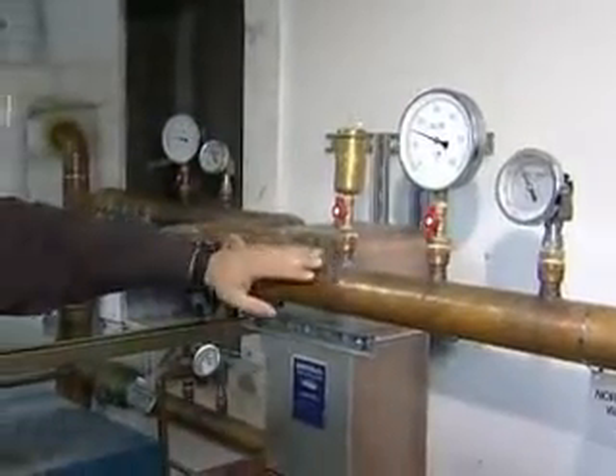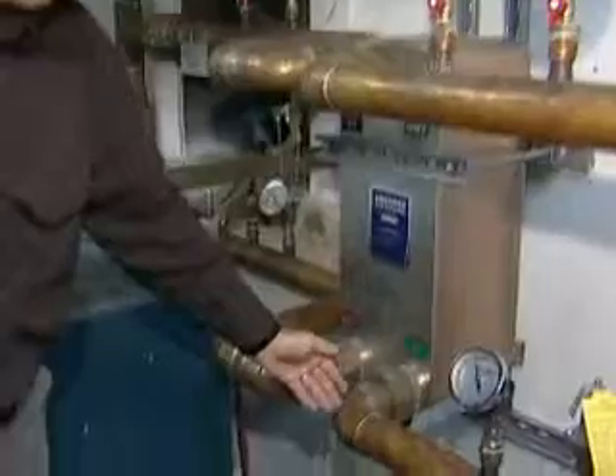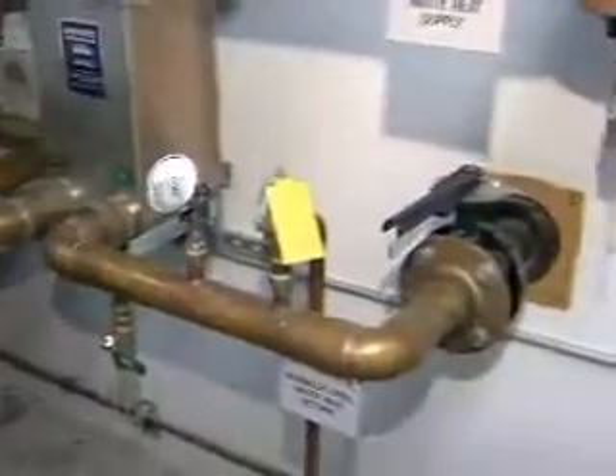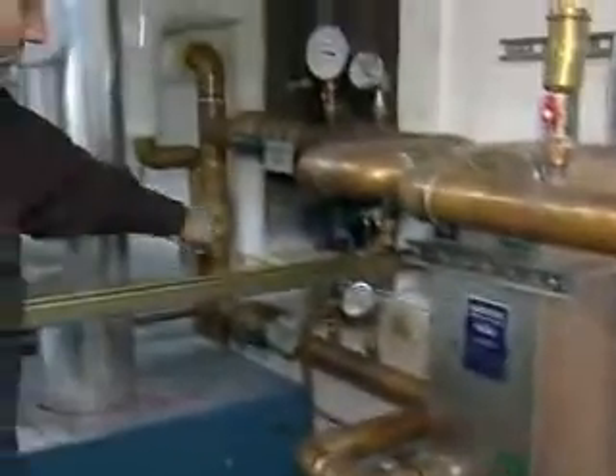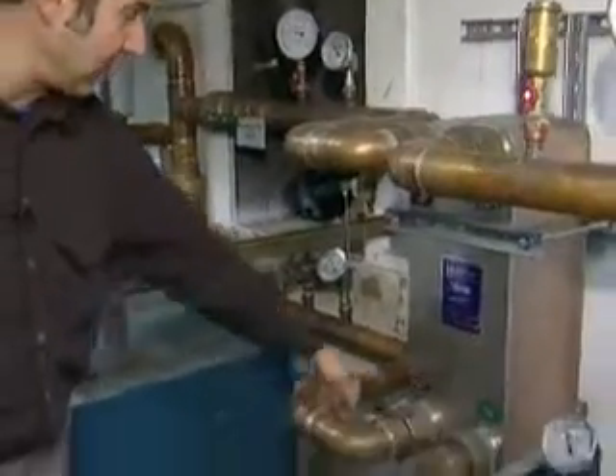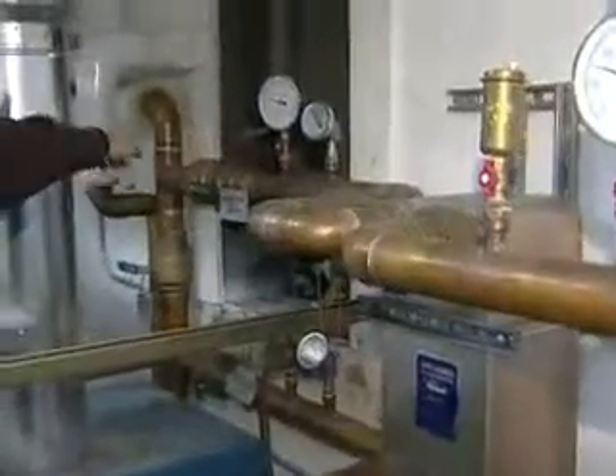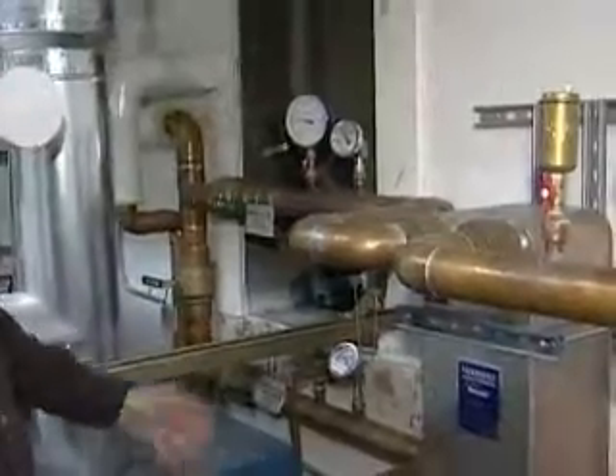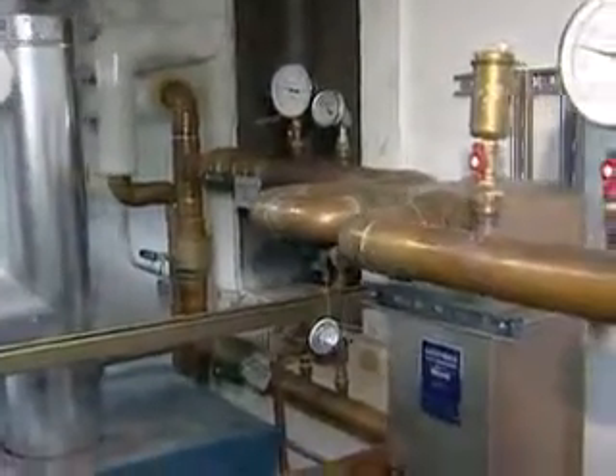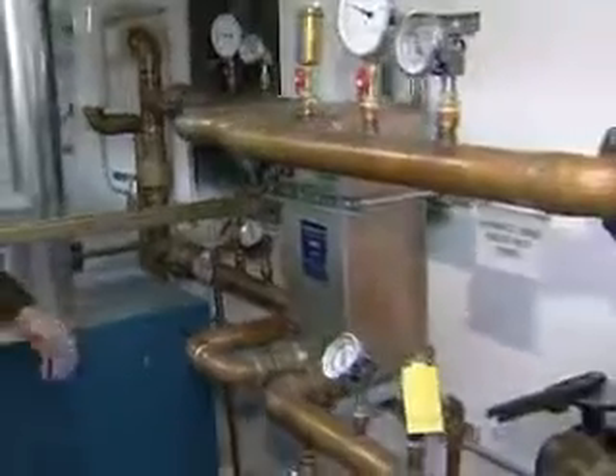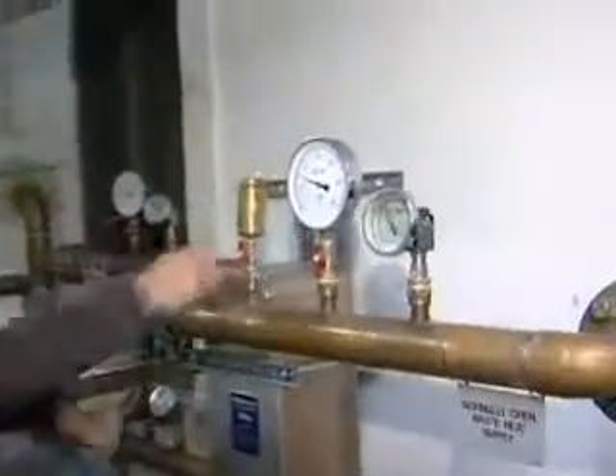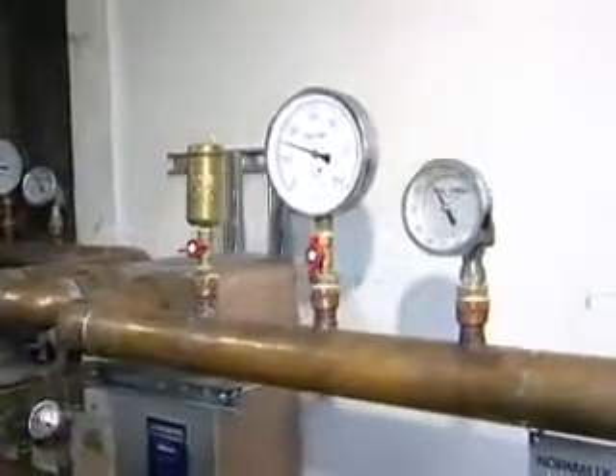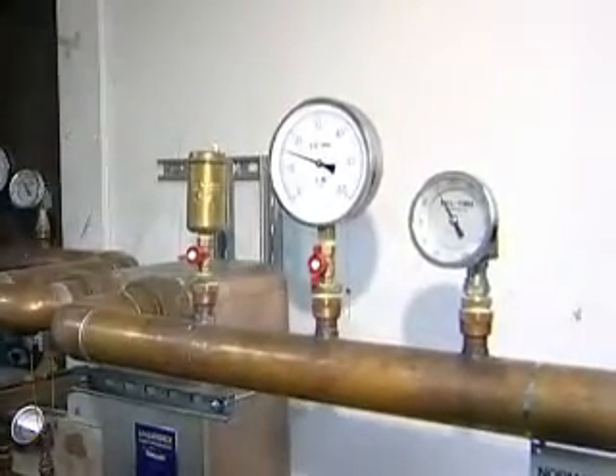So the hot water from the power plant comes in, goes through this side of the heat exchanger, back out. And then on the other side we have the cool water from the building heat comes in through the heat exchanger and goes back to the boiler. And so we have normally open valves that are tagged, they just leave open. And really all you need to do on this is check it periodically, check the temperatures, make sure we've got adequate pressure. And this air vent we would normally leave the valve closed off, and then we would open it periodically to bleed the air out of the system.